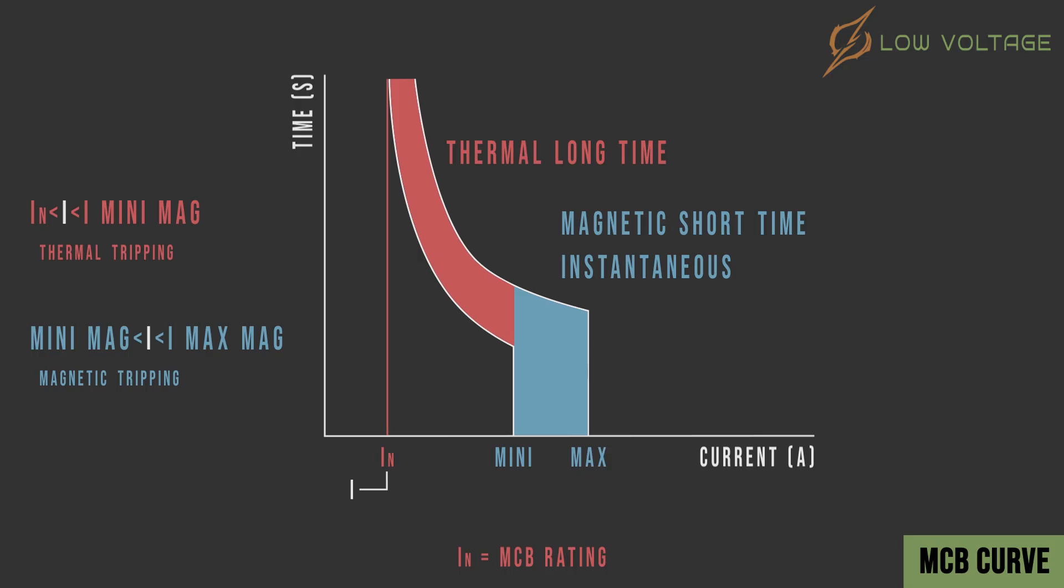Now if the current is before IN setting, the MCB will not trip. And if the current is after maximum magnetic setting, the MCB will trip in short instantaneous time, but at risk of fire hazard or damage depending on the intensity of the fault.